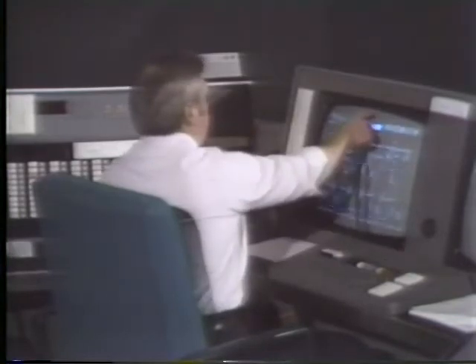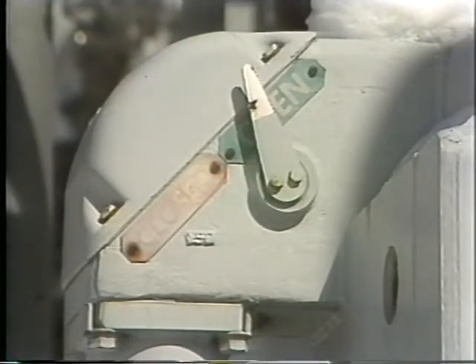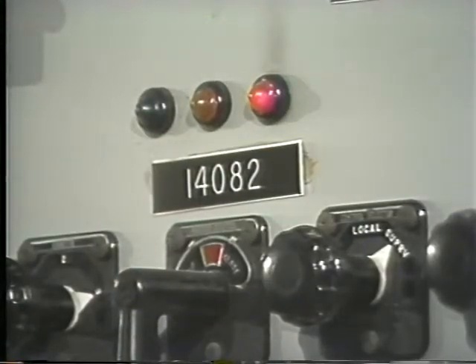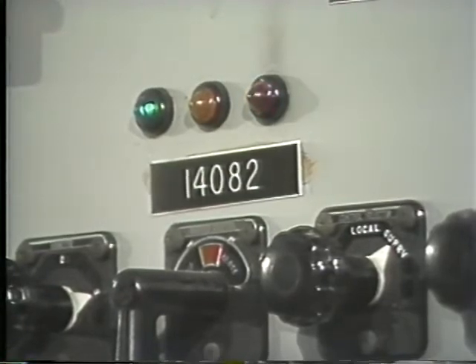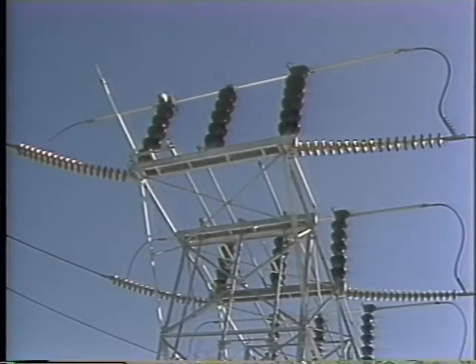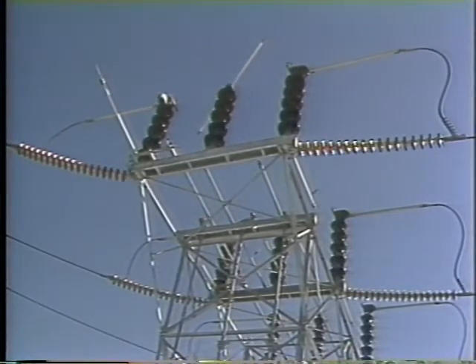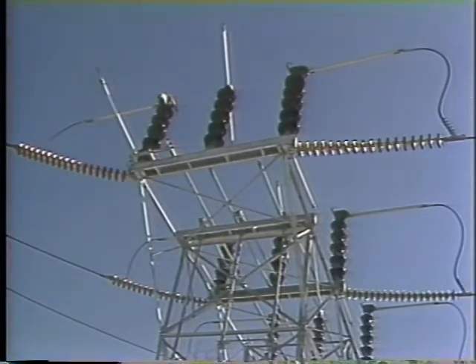On this job, the process starts with calling the dispatcher to get clearance for the work. The dispatcher is responsible for rerouting the load and performing the initial switching. In this case, a transformer primary has to be isolated from a 230 kV line. By remote control, the dispatcher unloads the transformer by opening the secondary breaker. Then he cuts power to the transformer by opening the primary breaker. He also isolates the primary by actuating a motor-operated disconnect switch on the incoming line.